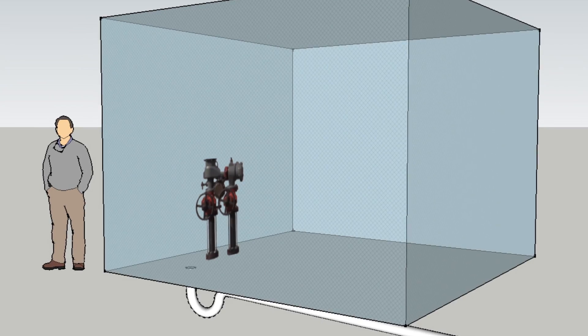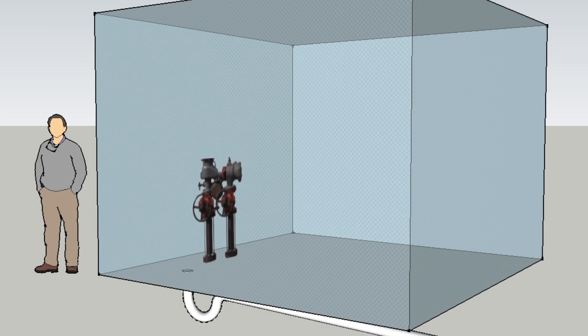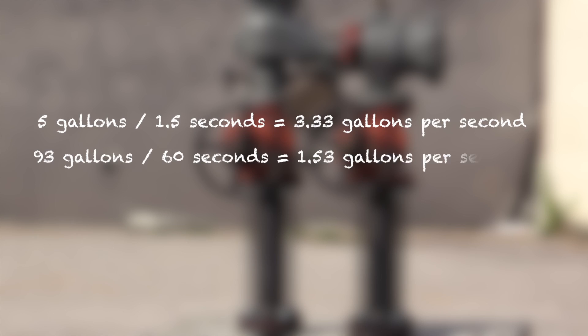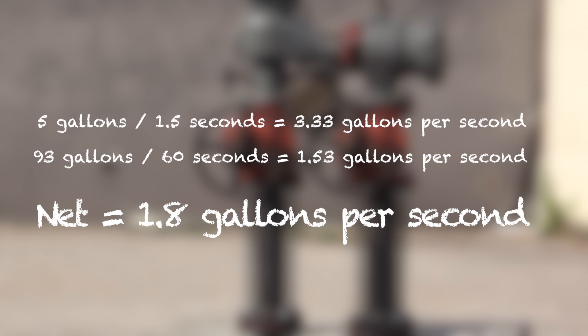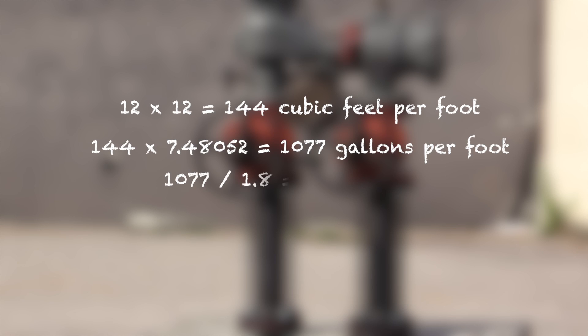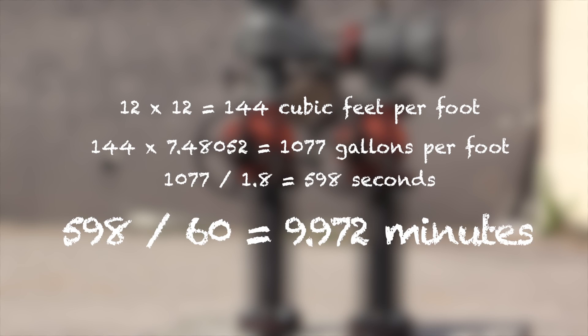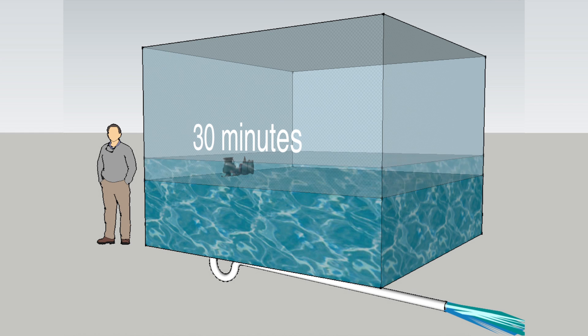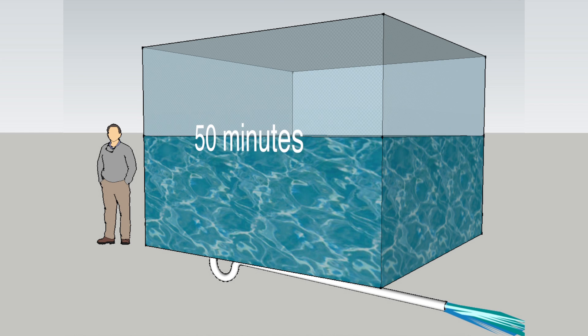Let's say this unit is in a 12 by 12 mechanical room with a typical four-inch drain. A little dumb guy math shows that that drain system will clear 1.8 gallons per second. A little more math reveals that even with the drain included, that's about a foot of water every 10 minutes. Real-world testing confirms that even the smallest flange-sized backflow preventer is a true flood hazard.